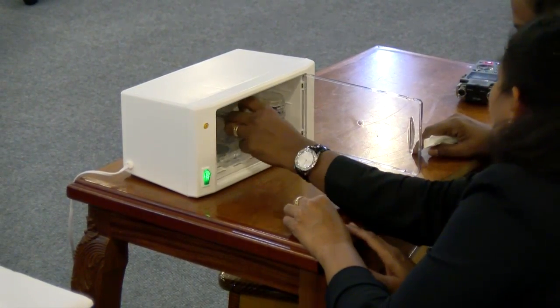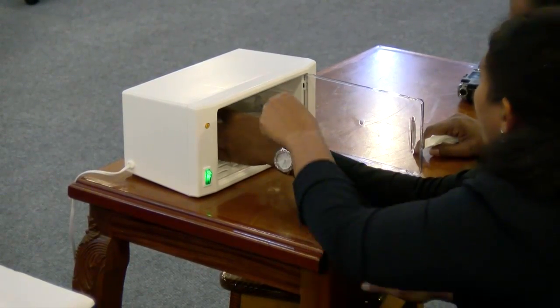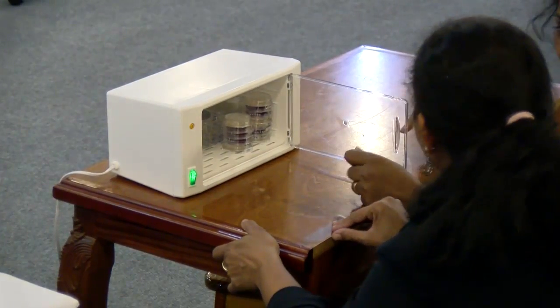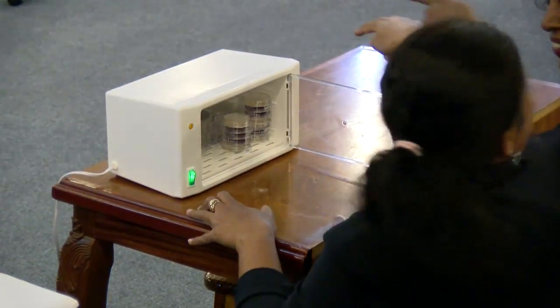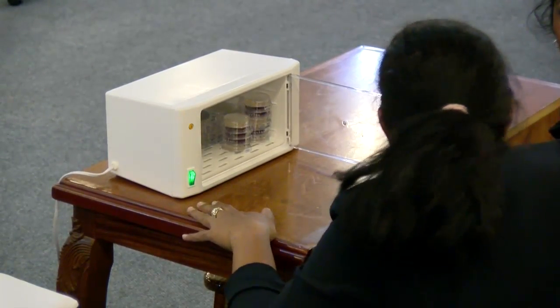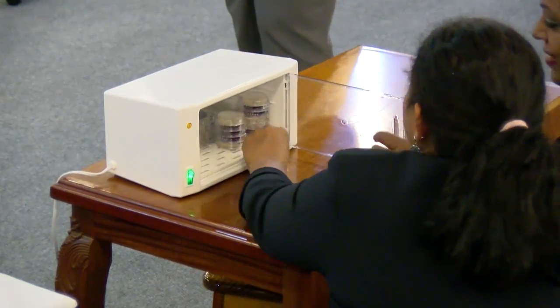With the glass petri dishes, you can stack until it falls down. How do you control the temperature of the incubator? It has a thermometer inside, but for microbiology you choose a temperature plus or minus 1 degree. So it's a very broad range. Unless you are analyzing some specific thermosensitive bacteria, for total count and the majority of bacteria, you can incubate from 35 to 37. So whatever incubator you have, it's good.